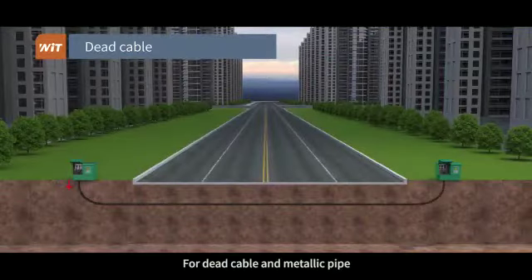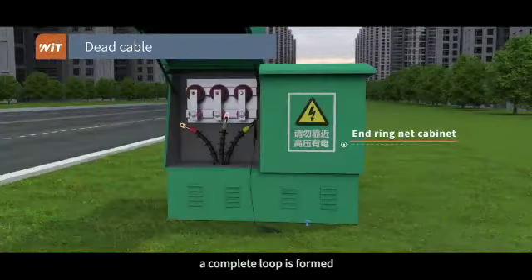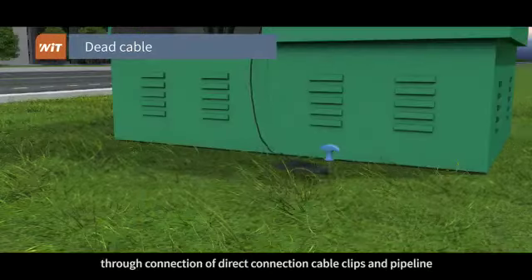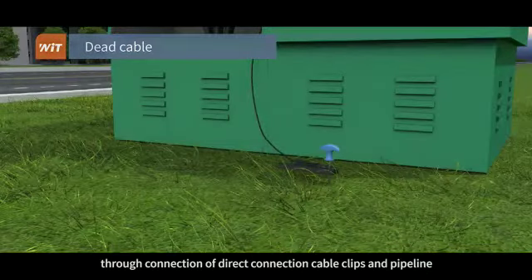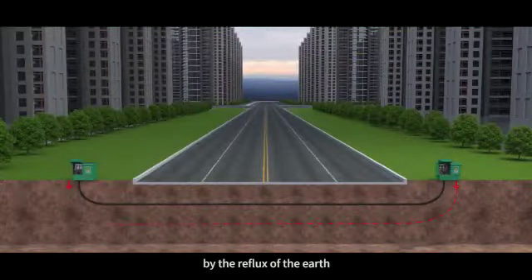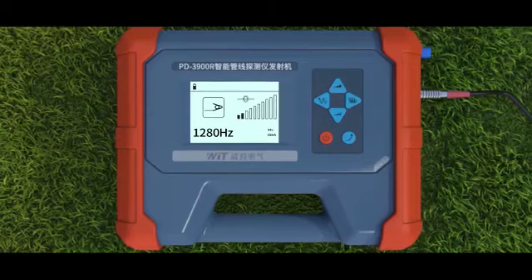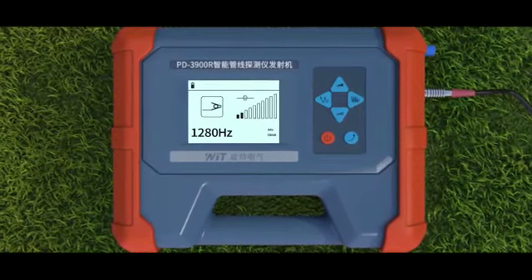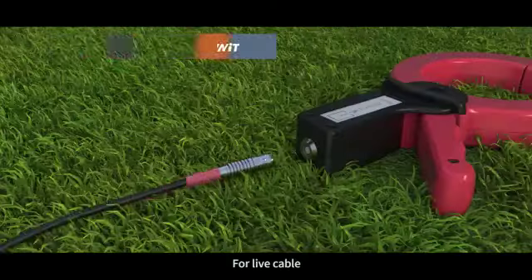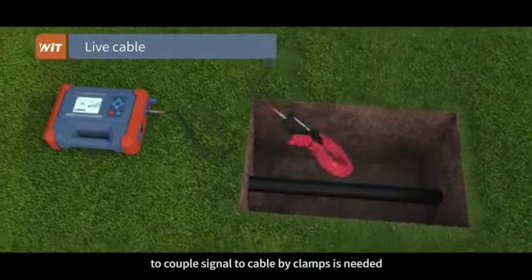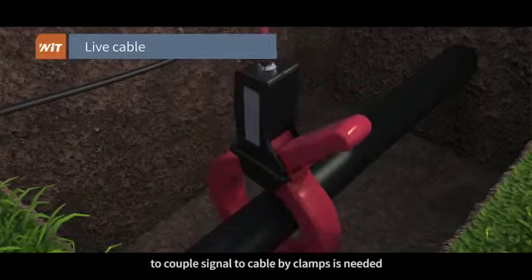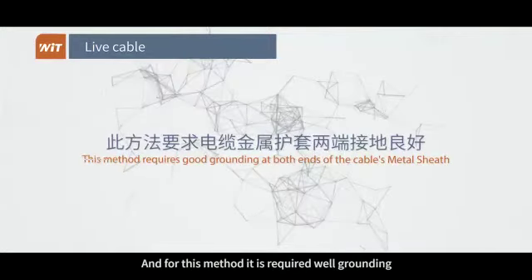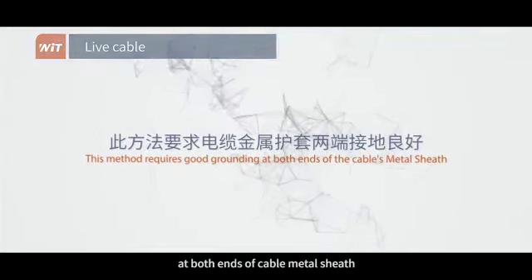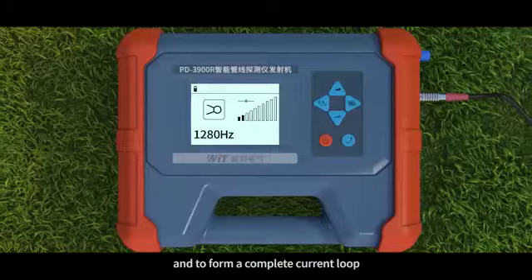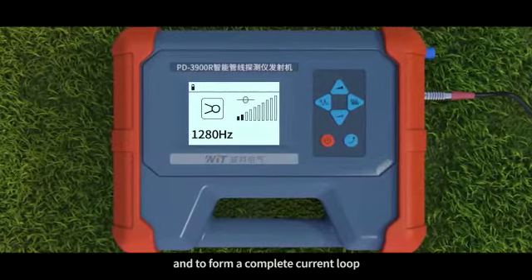For dead cable and metallic pipe, a complete loop is formed through the direct connection cable, clips, and pipeline, by the reflux of the earth. For live cable, coupling the signal to the cable by clamps is needed. For this method, good grounding at both ends of the cable metal sheath is required to form a complete current loop.